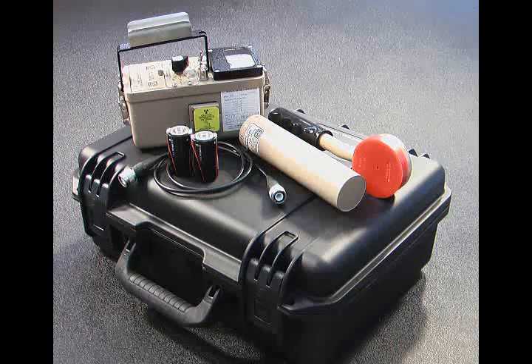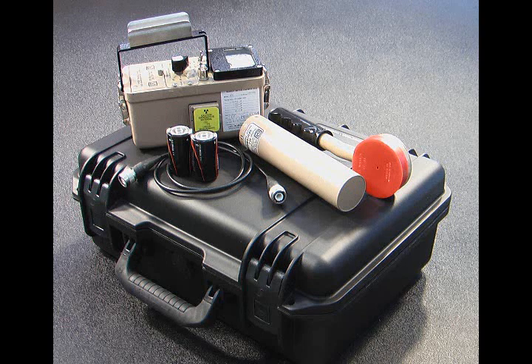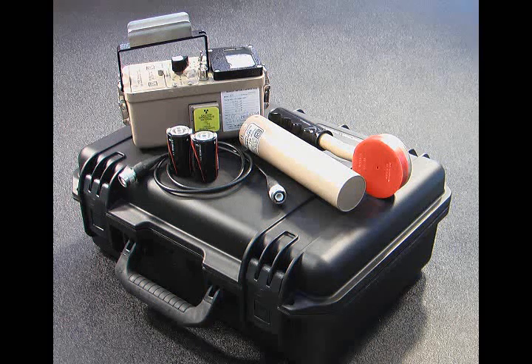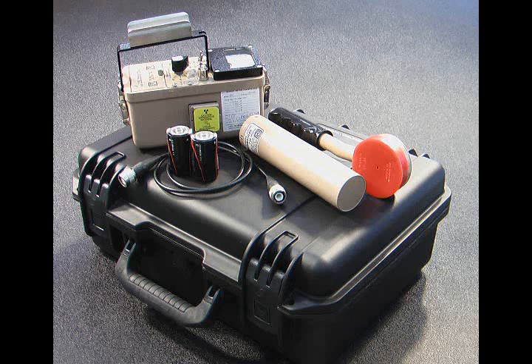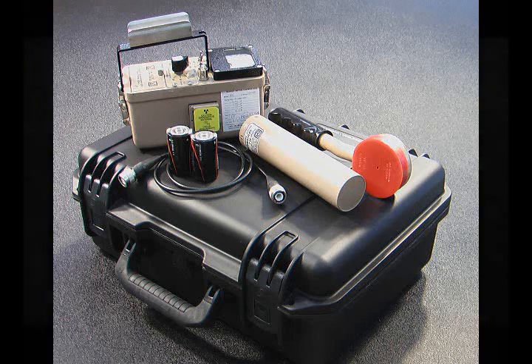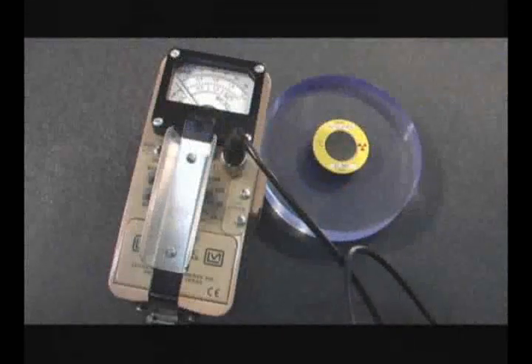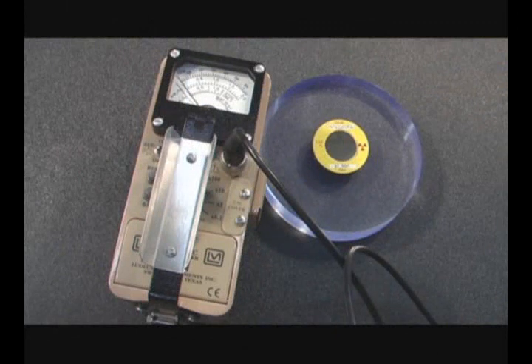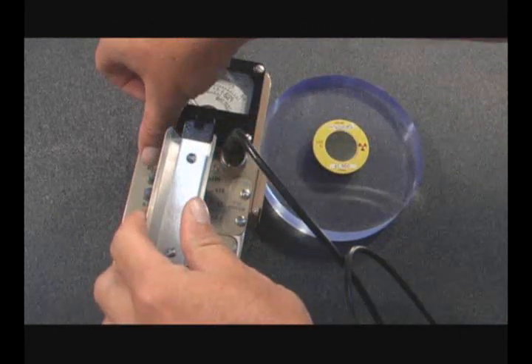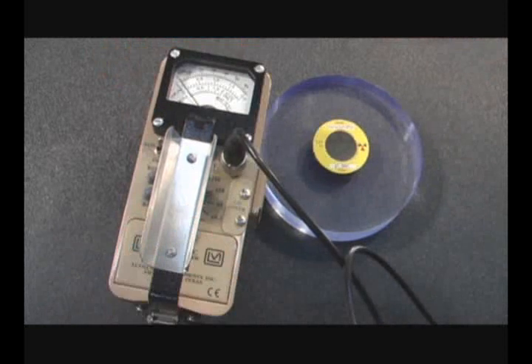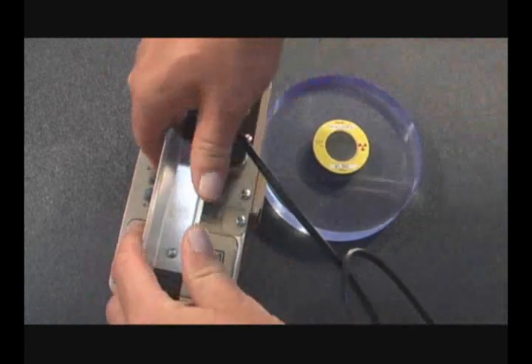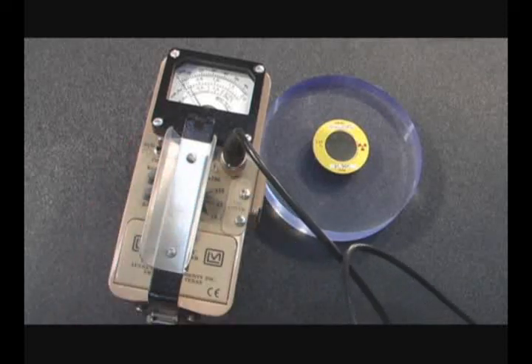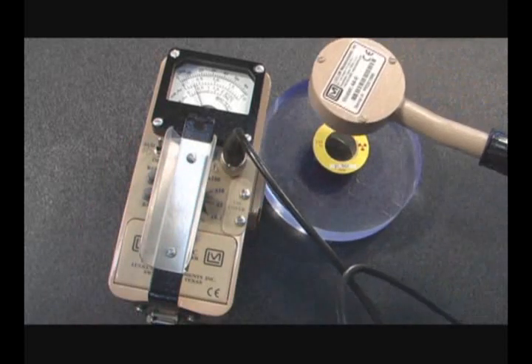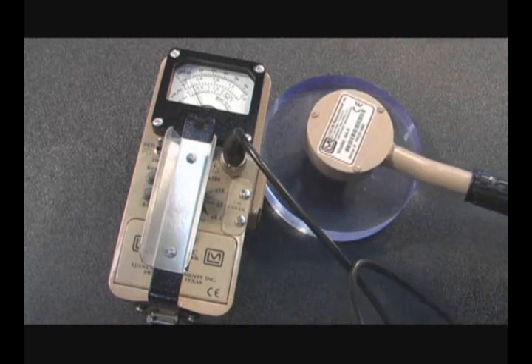In this next demonstration, the Model 44-9 will be used to show the detector's response to different types of radiation. Remember that the Model 44-9 detector will detect alpha, beta, and gamma radiation. Turn the audio switch on the Model 14C to the on position. Turn the range multiplier switch to the times 0.1 position. The Model 44-9 is held with the detector surface a few inches from an alpha source and moves slowly around to survey the entire area.